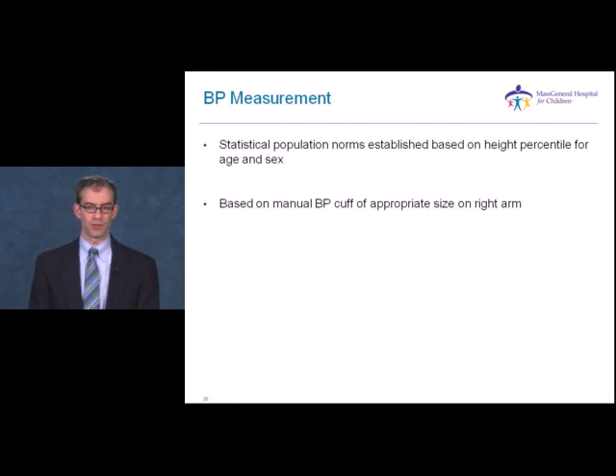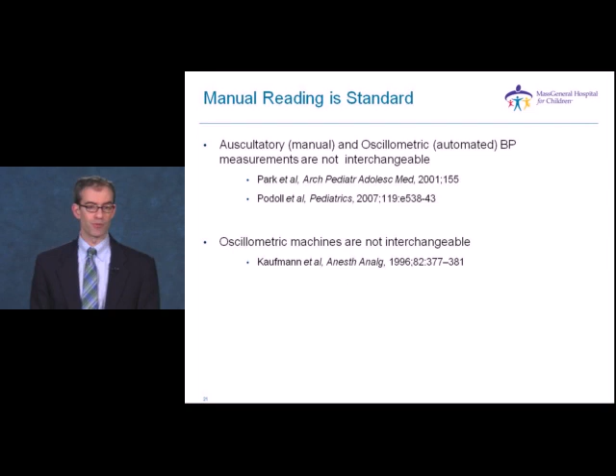The earlier studies suggest that the machines tend to raise blood pressure about 5 to 10 millimeters of mercury over manual readings. So any reading taken with a machine that is questionable should be repeated with a manual cuff. Also important is that a small cuff raises blood pressure, and so that can give you a falsely elevated reading. In contrast, a large cuff can give you a falsely lower reading, but that effect tends to be less dramatic.